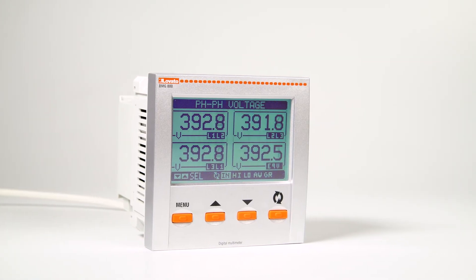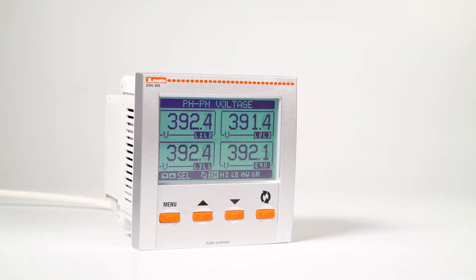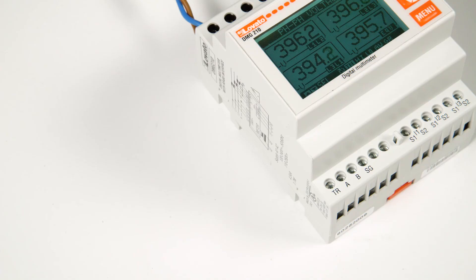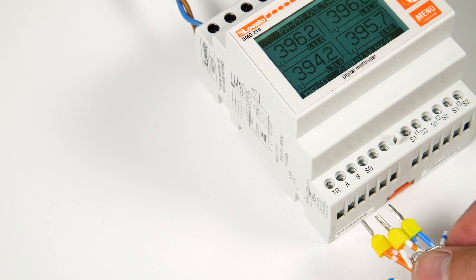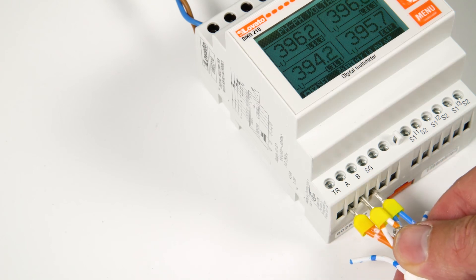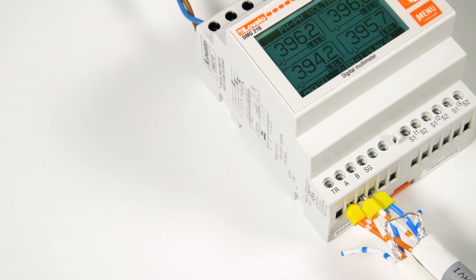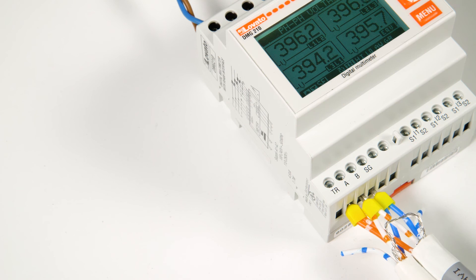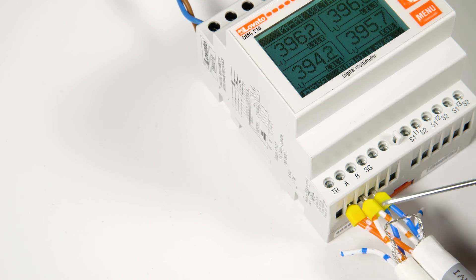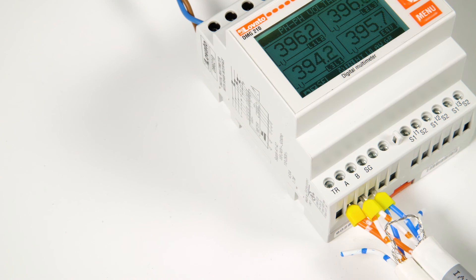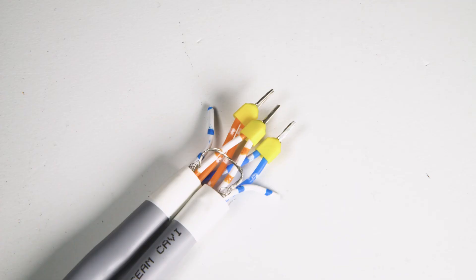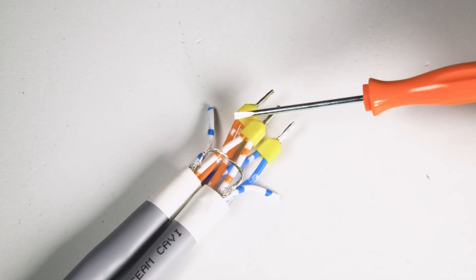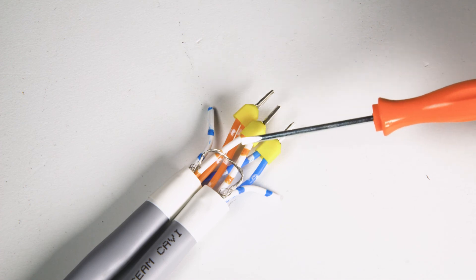Now, you can connect the devices through RS-485 shielded twisted pairs. For the first instrument of the network, a DIN rail-mounted DMG-210, connect pairs A, B and the negative reference SG with an in and out connection. This connection must be used for all intermediate devices in the network.